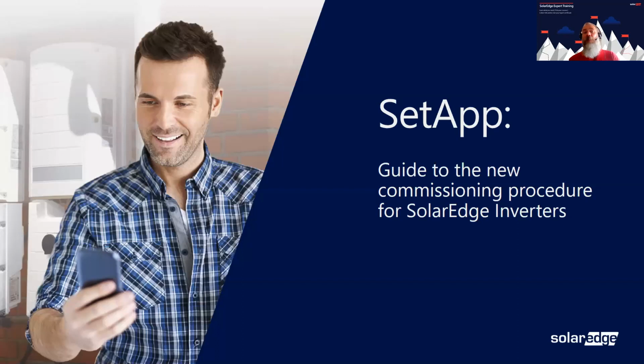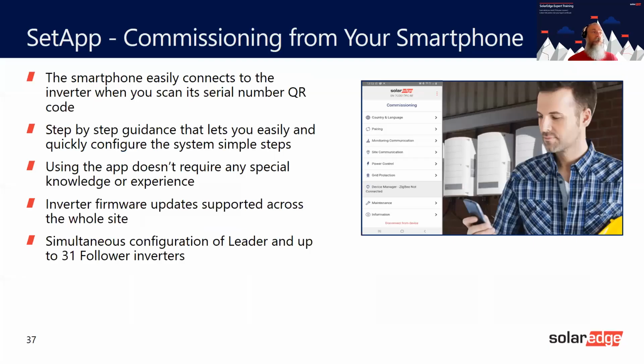So this is SetApp. Prior to, I'd say, 2019, we had LCD screens on our inverters, and we've changed them. So there are no screens on the newer inverter, and we have to have a means of communicating with this inverter to set it up, and that is how we use the SetApp. This again is free. You simply go to your App Store or Google Play and download SetApp. There are a couple of other apps on there: the My SolarEdge app and the monitoring app as well. But basically, it allows you to scan the QR code on the inverter. You can see on here where the QR codes are. It allows you to scan them and gain information.